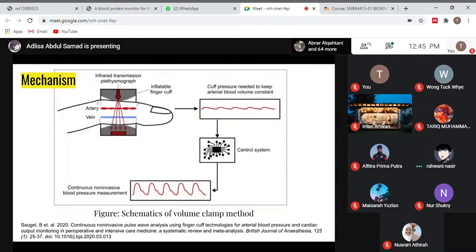Next, from the figure shown, we can see that the cuff contains the infrared transmission and plethysmograph sensors so that the cuff will measure the blood volume. And after that, the cuff will inflate or deflate continuously. So after that, the signal of the cuff pressure needed to keep arterial blood volume constant goes to the control system or algorithm, and lastly the continuous non-invasive blood pressure measurement is obtained. Next.